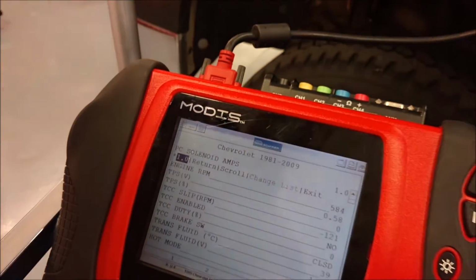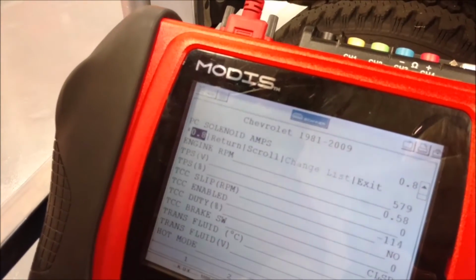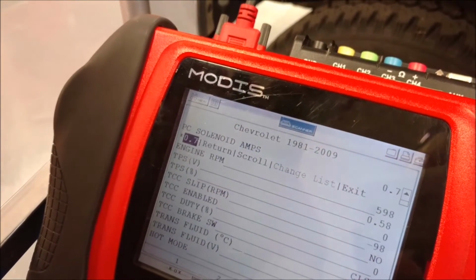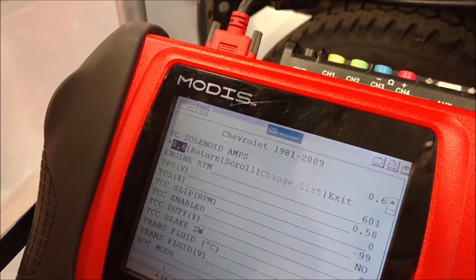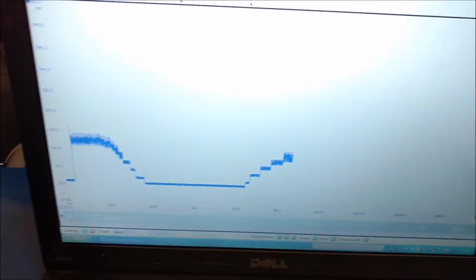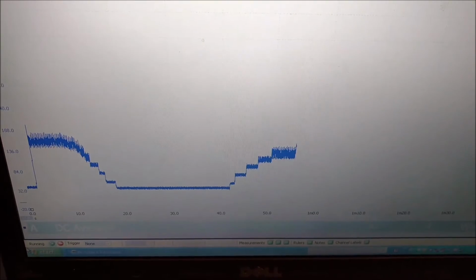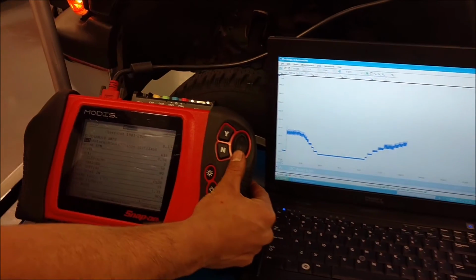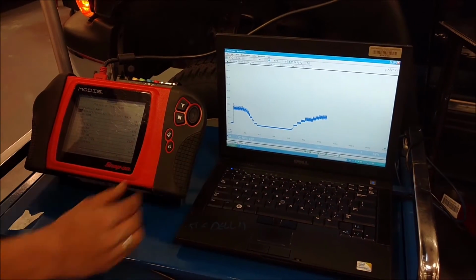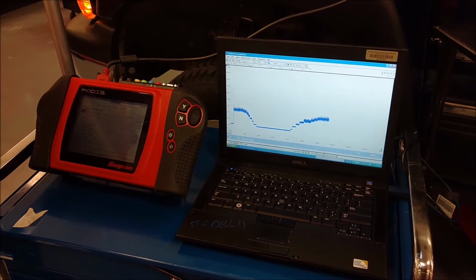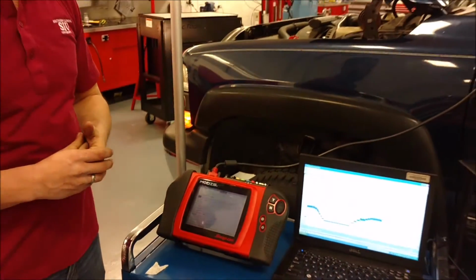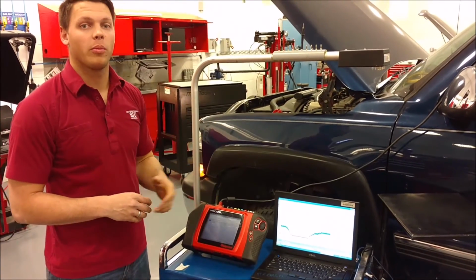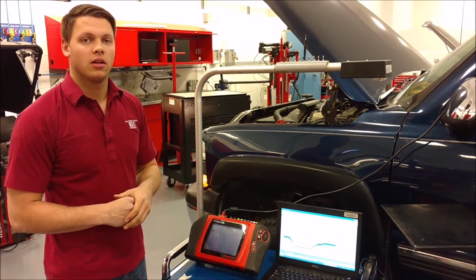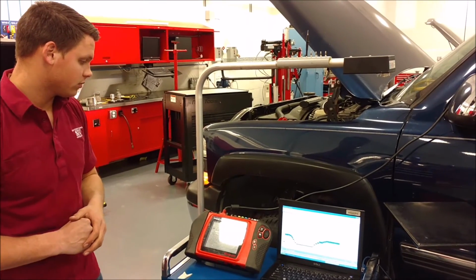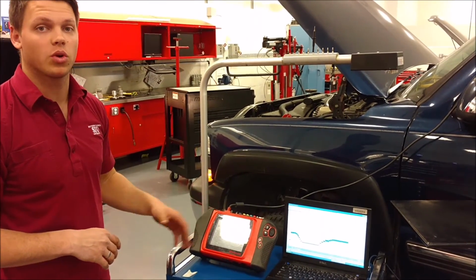As we start going back down in amperage, the pressure will begin to increase. This is also a good diagnostic procedure to make sure the oil pressure is sufficient. Also, this is a good way to see if the solenoid is working properly.